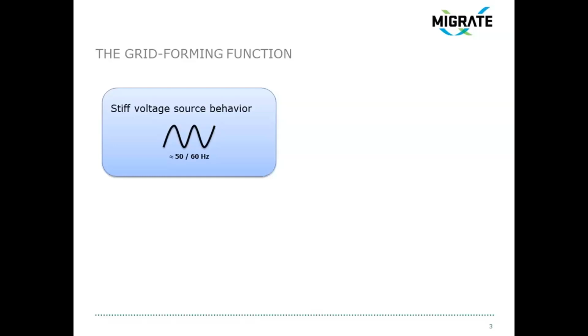You need to be strong, because you need to be like a reference signal for other sources that want to synchronize on you, like other grid following units. It can be other synchronous machines, or it can also be other grid forming units. In the MIGRATE project, we consider that we don't need any telecommunication or synchronization.